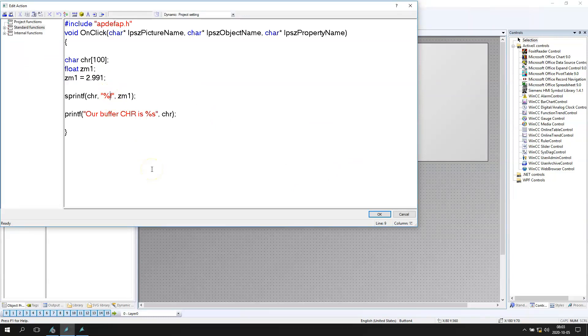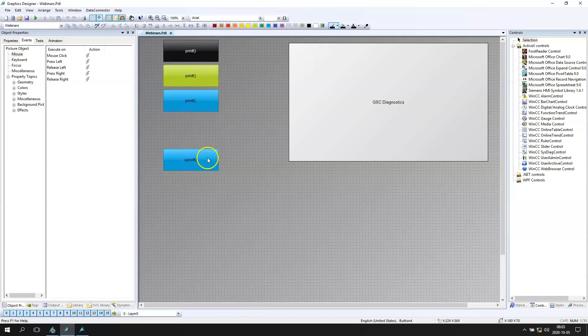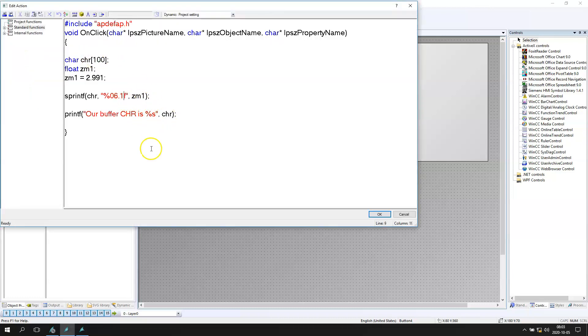As I said, we can change the formatting. For example, we can put %06.2f so we have a zero-padded number on the left side. With one decimal place after the dot, after clicking the button we get 0003.0 because 0.991 rounds up. Then when we put two places after the dot, we get 2.99. After running WinCC we can see the zero on the left side and two point nine nine.